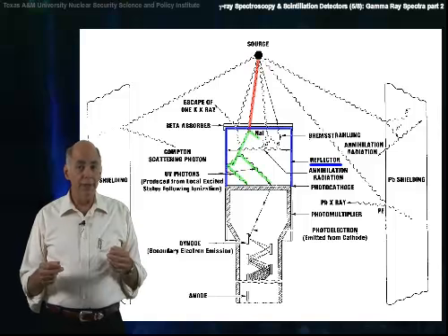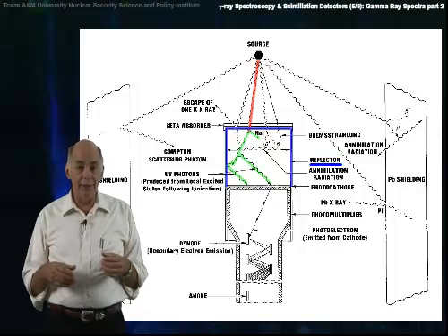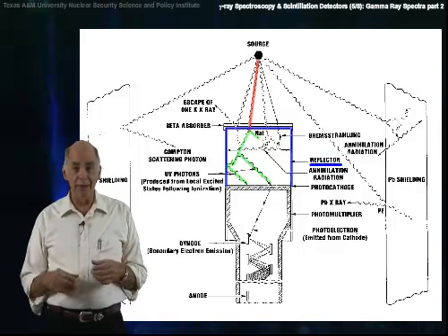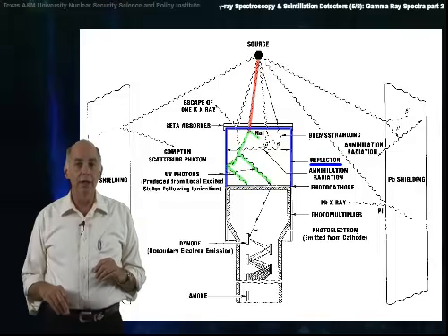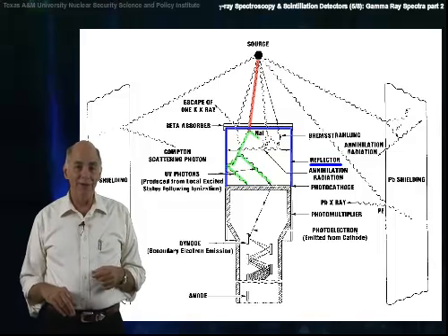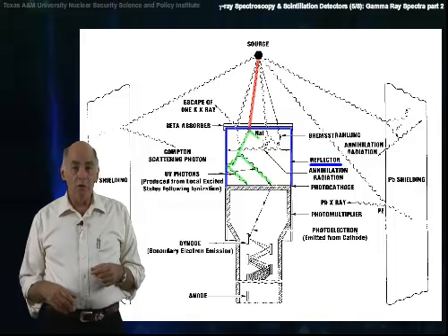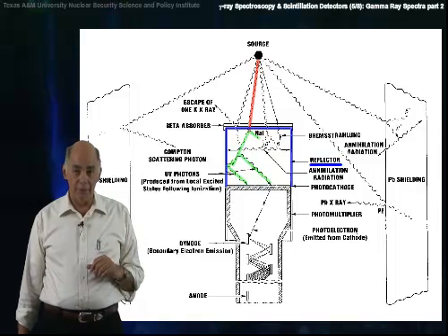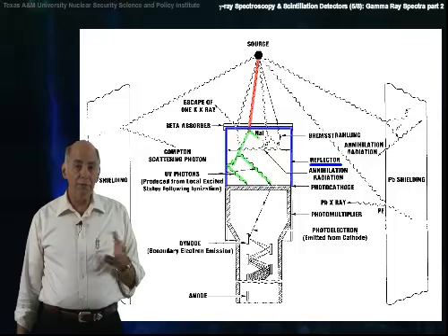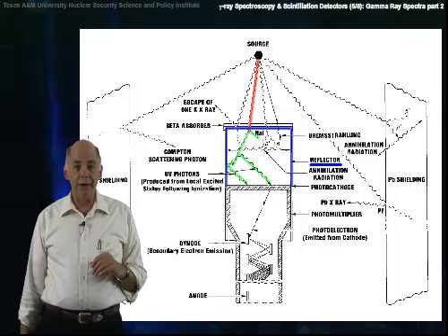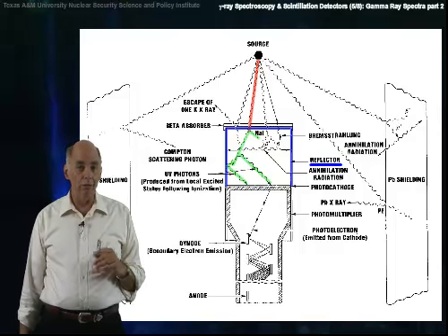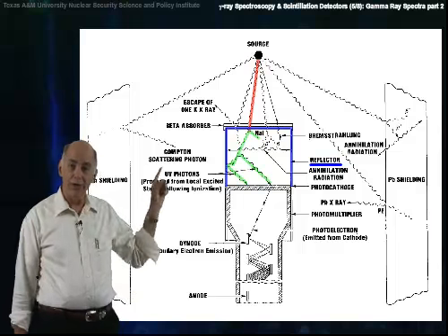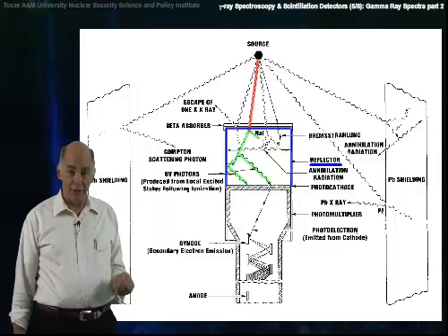Some of these UV photons bounce around in the detector, guided by reflectors surrounding the scintillator, and some head in the right direction at birth. But overall, fewer than a third will strike the photocathode. About 10% of those photons striking the photocathode will free an electron and start the cascade down the dynode string.